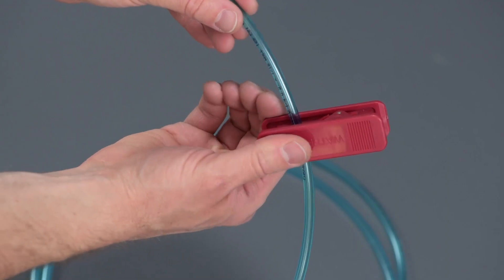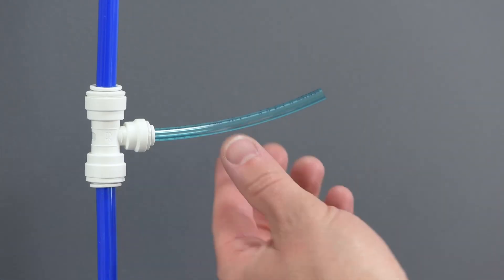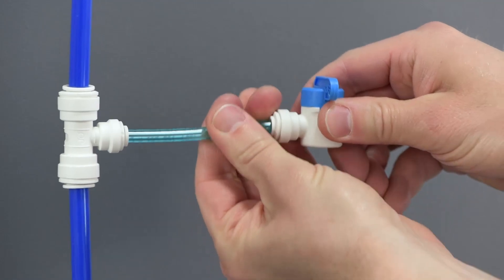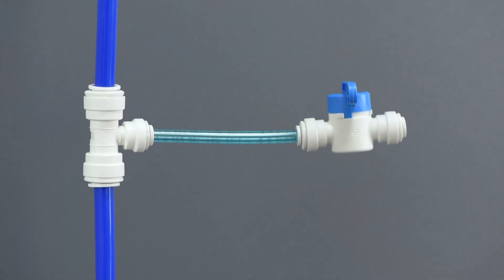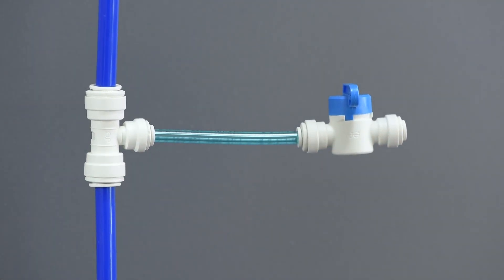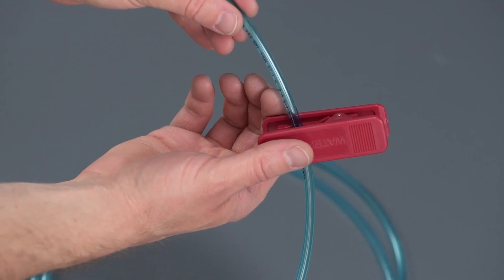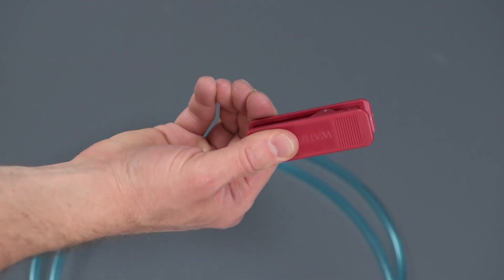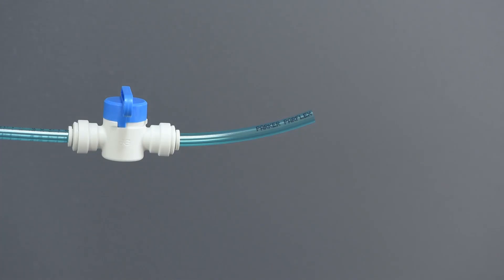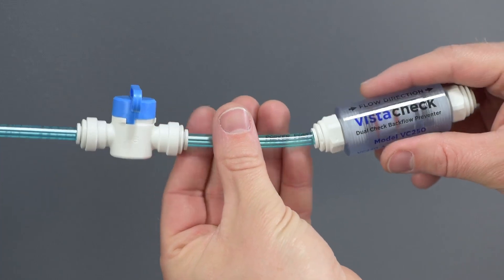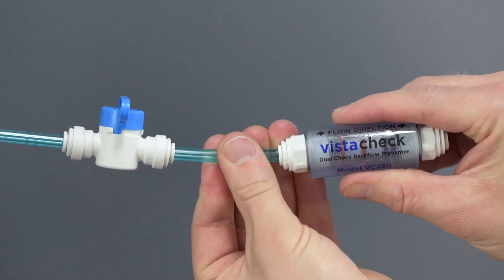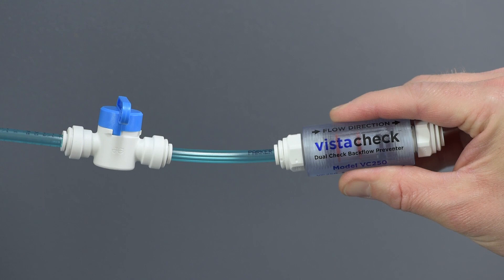Next, cut a 3 to 4 inch piece of the blue poly tubing and connect the installed fitting from our last step to the inlet of the inline water valve provided. Be sure the valve is in the closed position. That blue lever should be 90 degrees relative to the valve body. Cut another 3 to 4 inch piece of blue poly tubing and connect one end to the outlet of the inline valve and the other end to the inlet of the supplied CSA certified VistaCheck DualCheck backflow preventer.